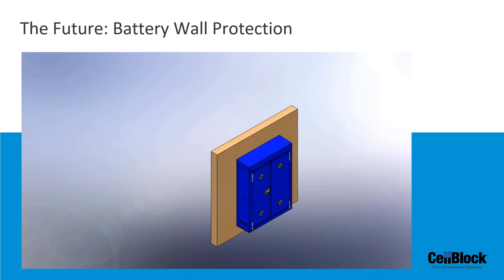There's a lot of energy involved in these things, and there's not a lot of specifications on how to deal with it. The National Fire Protection Association has put out a standard recently called 855. It's trying to put some definition around how to address these ESS systems. I will say that I don't think they're far enough with the standard yet, because they're still telling you to extinguish it with water, which we know does not completely extinguish a lithium-ion battery fire.